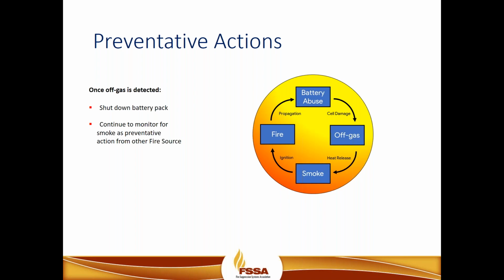Now, I mentioned smoke detection is a critical stage at which thermal runaway occurs. But in this particular case, what we're talking about with smoke detection is external factors. So this will allow stakeholders to shut down equipment, and eliminate the overcharging or overheating abuse factor that is occurring. And then monitoring for external fires with early warning smoke detection, in the space or external to the battery module or the battery management system or the energy storage system. So allowing us that critical time, that golden time, to be able to identify a threat from an external source. That's where early warning smoke detection really does play a critical factor. But they do need to work in conjunction with a battery management system in order to stop the abuse factor from occurring.